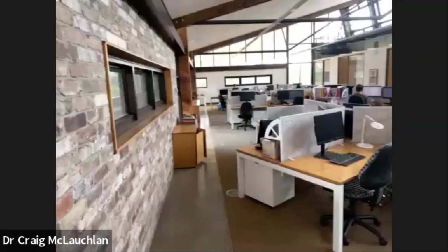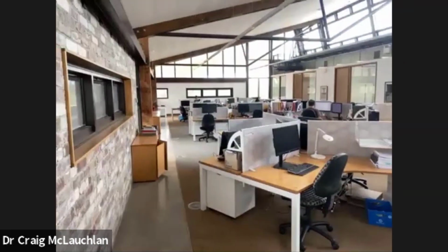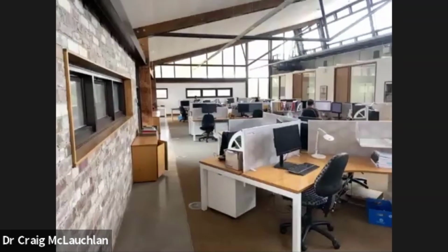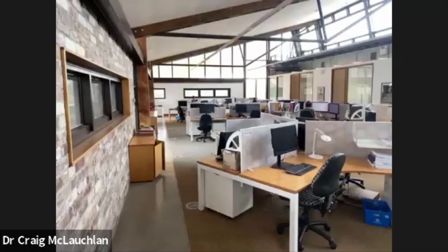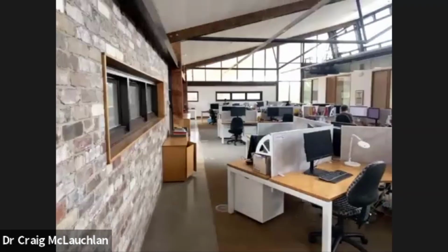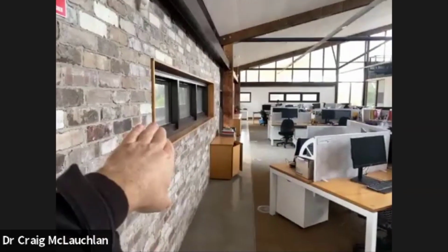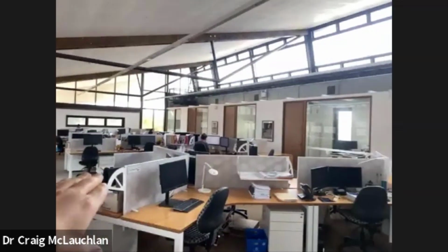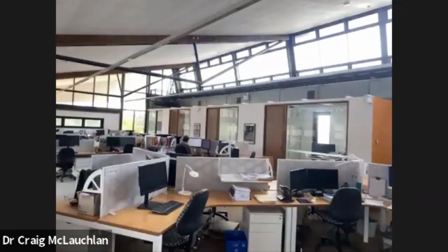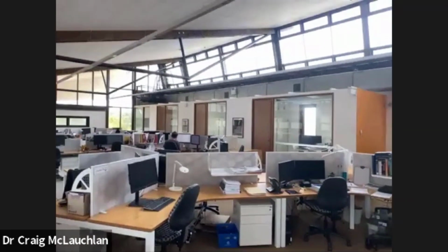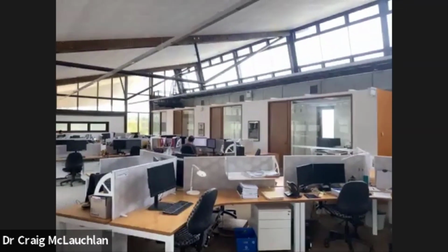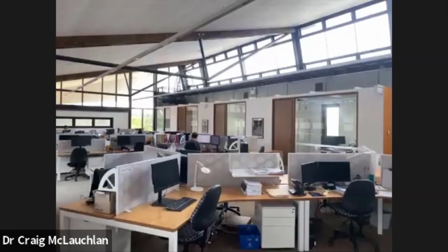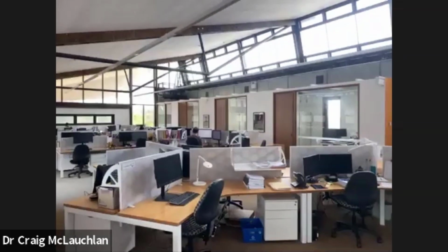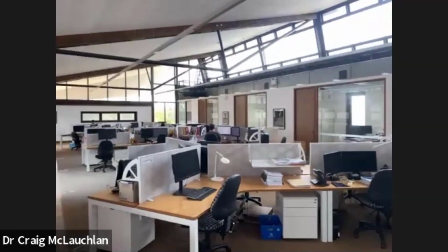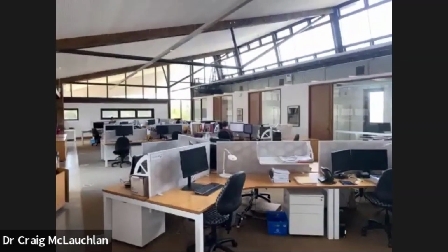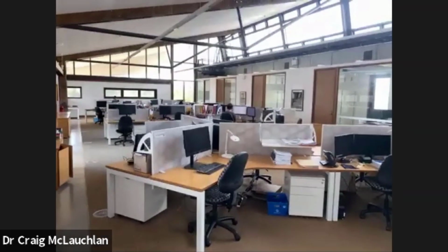We're also a mixed mode ventilating building. What that means is that whenever we can, we naturally ventilate, and only when that's not adequate do we heat or cool. To naturally ventilate, we've got operable windows down here at person height, and higher level operable windows up there. So if there's a breeze and we open the windows, we can catch the breeze across the building. But if there's no breeze, it utilises the stack effect to have buoyant heat draw cool air in from the lower windows while hot air goes out the higher windows.